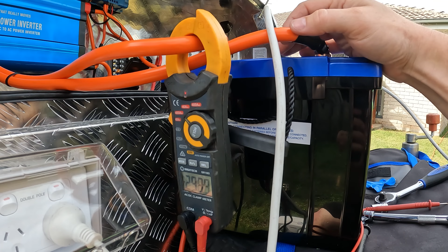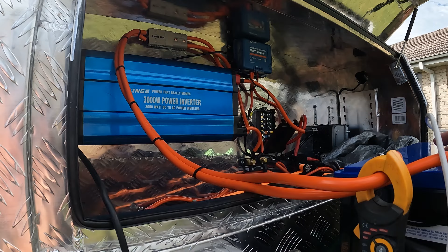So go to the 50mm cable at least, I would say, over a short run. This is fine just to do some testing, 35mm, but it's obviously not enough. The voltage sags too much for the inverter, but the inverter just keeps copping it, eh? I'm really impressed with that King's inverter and this battery. Yep, we're just on 11 minutes now, so that's quite impressive.